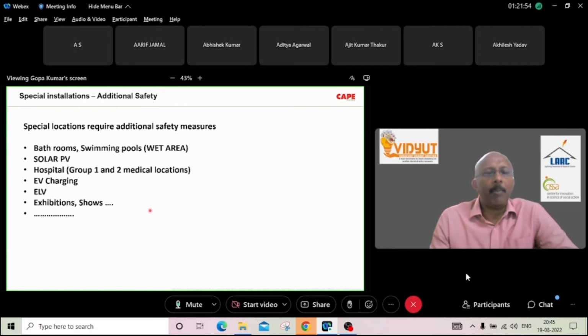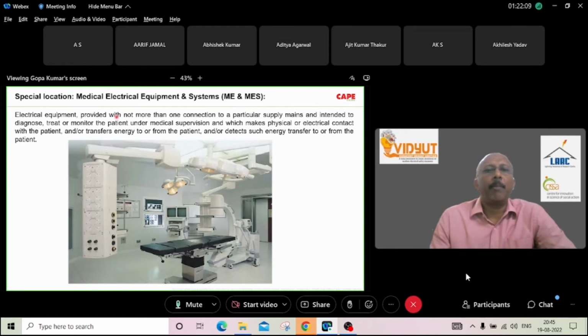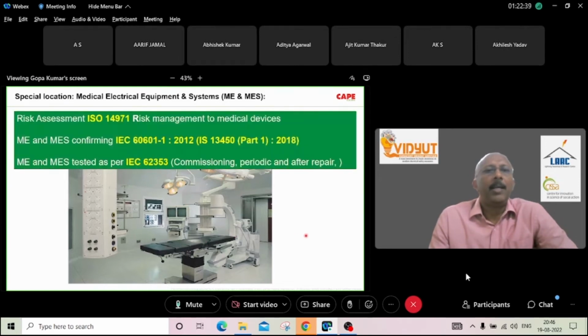So for that critical application, let's say, for example, control supply in a substation, you have to go for an unearthed system. So basically, these additional measures are also necessary depending upon the criticality of your building. Especially for hospitals, the medical equipment and medical systems are classified. There are about 300 plus ISO standards established for each and every biomedical equipment which is made and installed in this particular location. The hospital management should look at those standards and buy the equipment which satisfies those standards. Then once you install that equipment, you have to be careful and follow the rules and regulations written in the codes of practice.